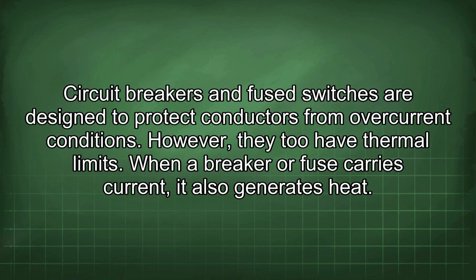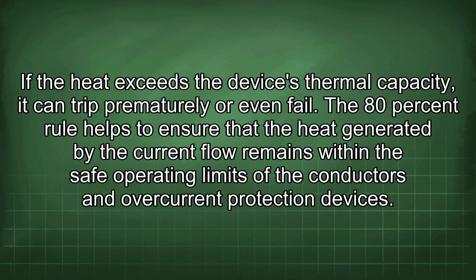Circuit breakers and fused switches are designed to protect conductors from overcurrent conditions. However, they too have thermal limits. When a breaker or fuse carries current, it also generates heat. If the heat exceeds the device's thermal capacity, it can trip prematurely or even fail. The 80% rule helps to ensure that the heat generated by the current flow remains within the safe operating limits of the conductors and overcurrent protection devices.